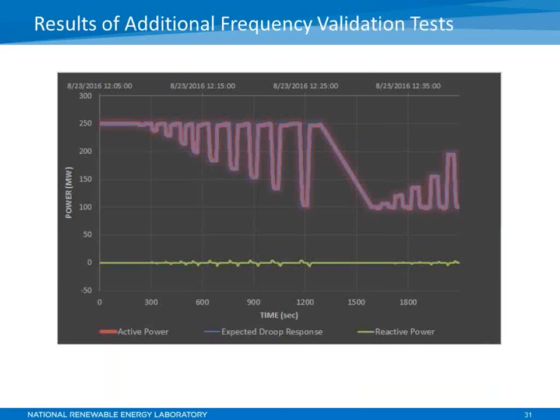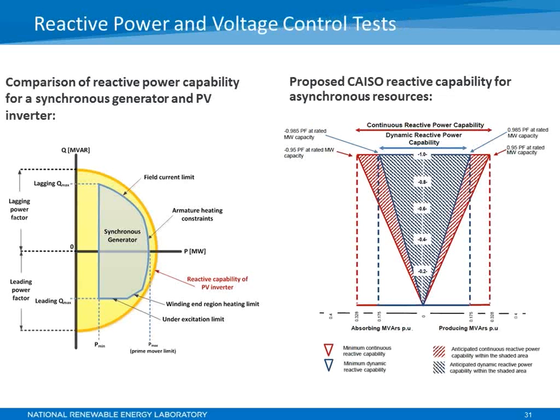This is an example of more standardized commissioning tests done by First Solar when a plant is responding to step changes in frequency, and you see that the calculated power response and the actually measured power response are basically on top of each other. So that shows that the plant can also provide fast frequency types of responses very efficiently. The other type of test we demonstrated here is a voltage regulation and reactive power control type of test.